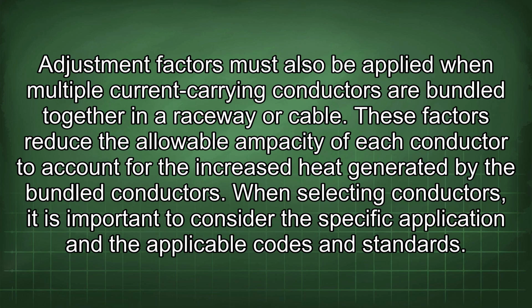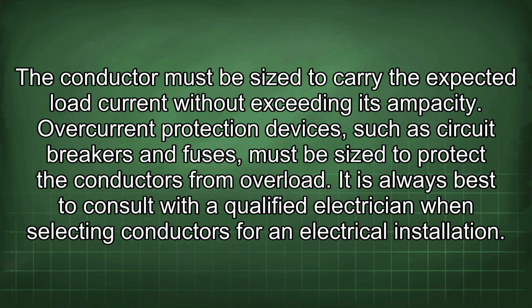When selecting conductors, it is important to consider the specific application and the applicable codes and standards. The conductor must be sized to carry the expected load current without exceeding its ampacity. Overcurrent protection devices, such as circuit breakers and fuses, must be sized to protect the conductors from overload. It is always best to consult with a qualified electrician when selecting conductors for an electrical installation.